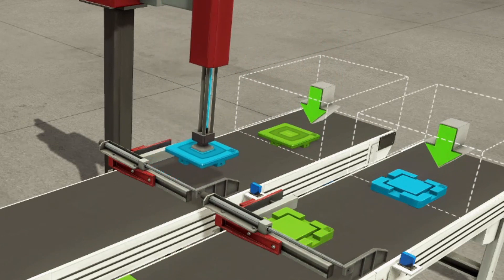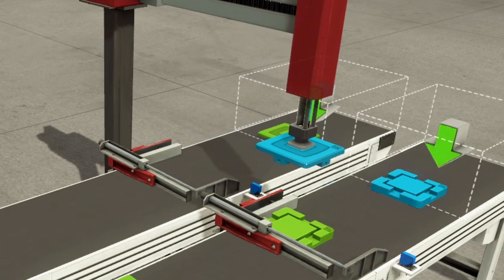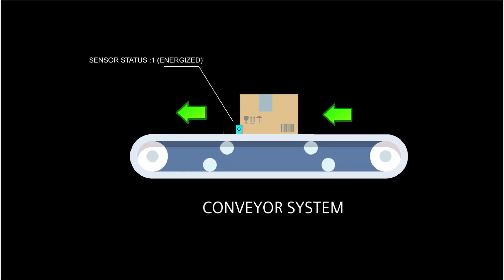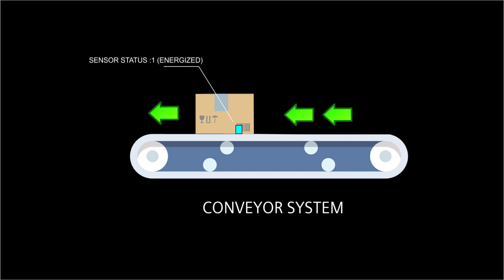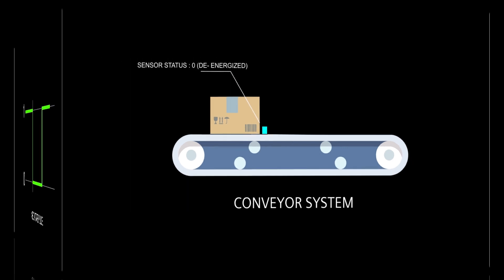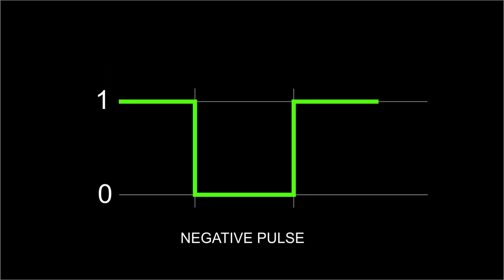In this case, we need a function that responds during a high-to-low transition state. Meaning, after the product energizes the sensor, the conveyor will continue to run until the product totally passes the sensor. What we need here is a negative edge trigger.